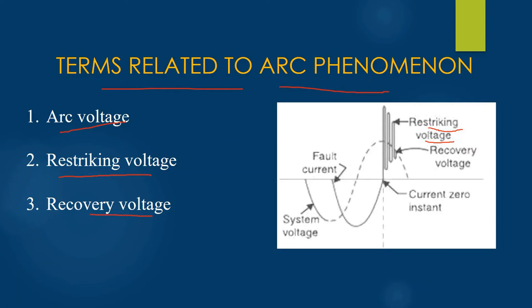The third term is recovery voltage. As you can see in the figure, the dotted line represents the recovery voltage. It is the normal frequency RMS voltage that appears across the contacts of the circuit breaker after the final arc extinction. It is generally approximately equal to the system voltage, and therefore you can see that the dotted lines basically represent your system voltage.